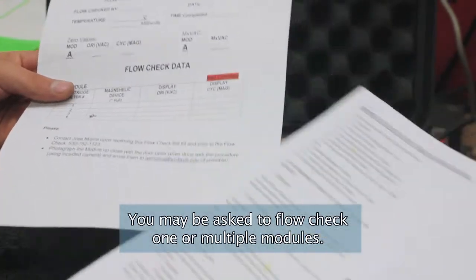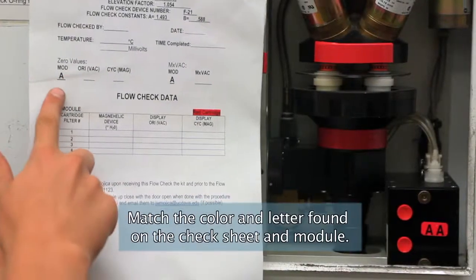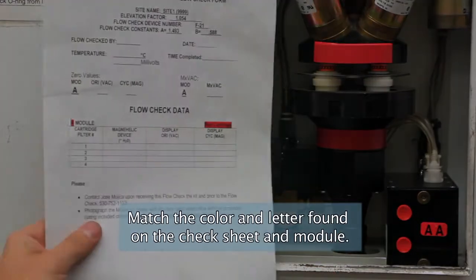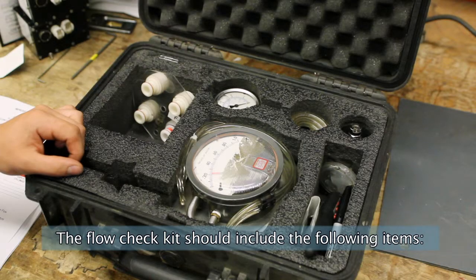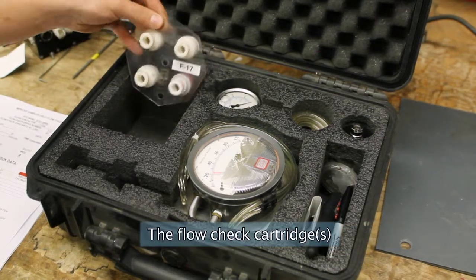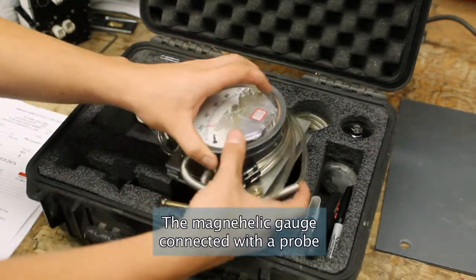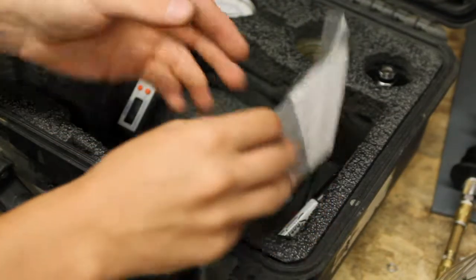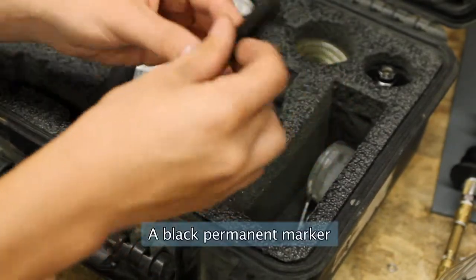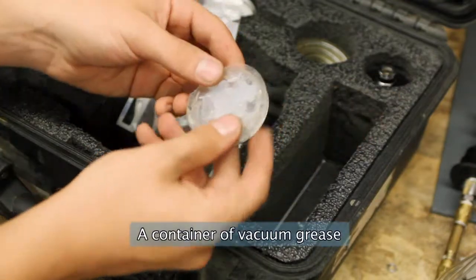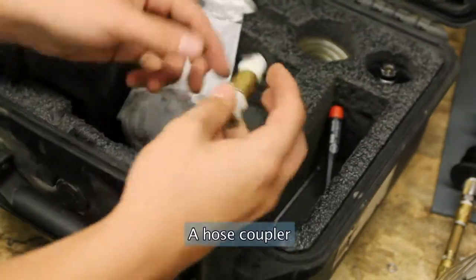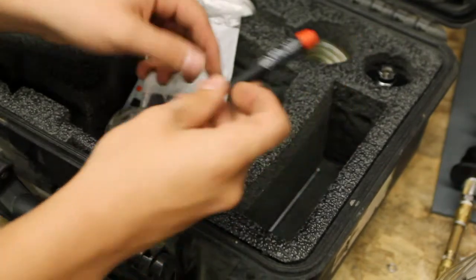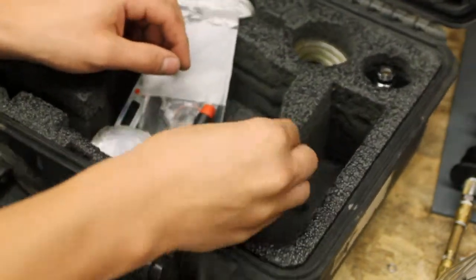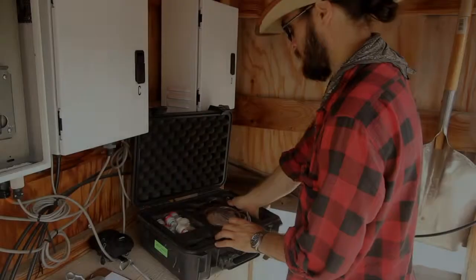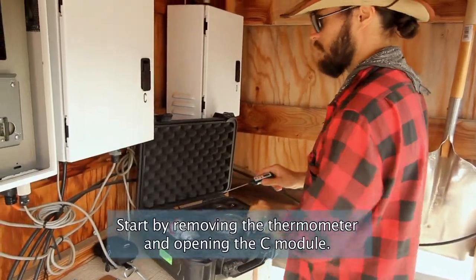You may be asked to flow check one or multiple modules. Match the color and letter found on the check sheet and module. The flow check kit should include the following items: the flow check cartridge, the Magnehelic gauge connected with a probe, a digital thermometer, spare O-rings, a black permanent marker, a container of vacuum grease, a hose coupler, a miniature screwdriver, and a hex key.